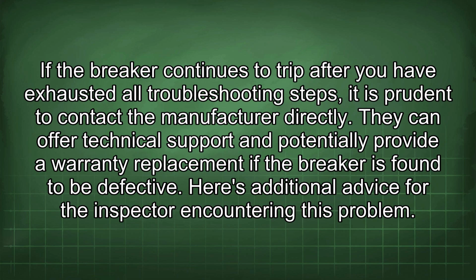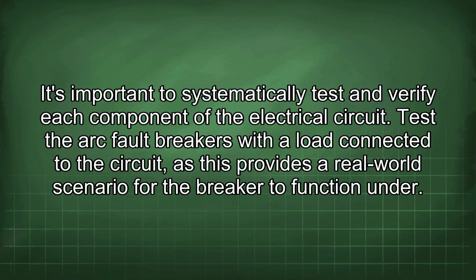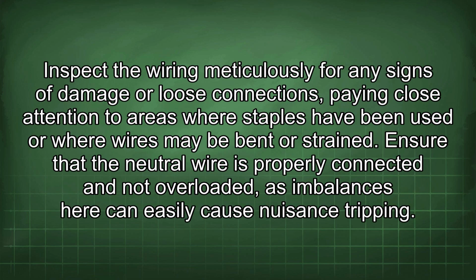Here's additional advice for the inspector encountering this problem. It's important to systematically test and verify each component of the electrical circuit. Test the arc fault breakers with a load connected to the circuit, as this provides a real-world scenario for the breaker to function under. Inspect the wiring meticulously for any signs of damage or loose connections, paying close attention to areas where staples have been used or where wires may be bent or strained.